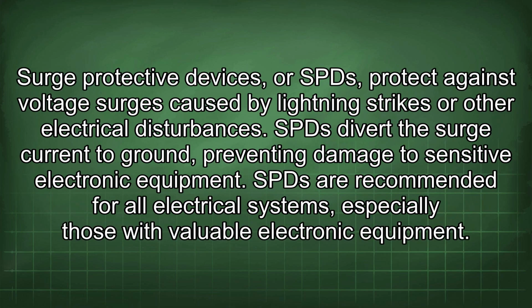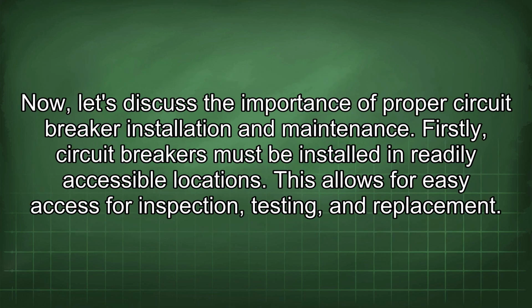Surge protective devices, or SPDs, protect against voltage surges caused by lightning strikes or other electrical disturbances. SPDs divert the surge current to ground, preventing damage to sensitive electronic equipment. SPDs are recommended for all electrical systems, especially those with valuable electronic equipment. Now let's discuss the importance of proper circuit breaker installation and maintenance.